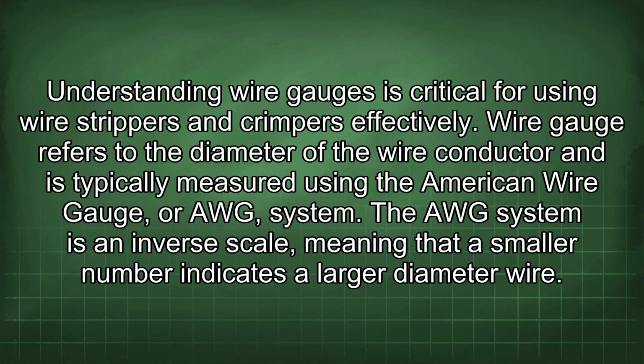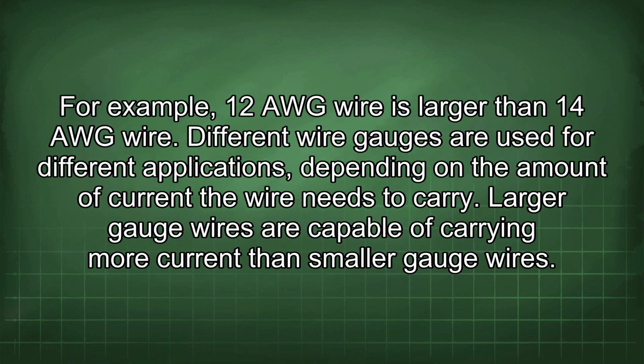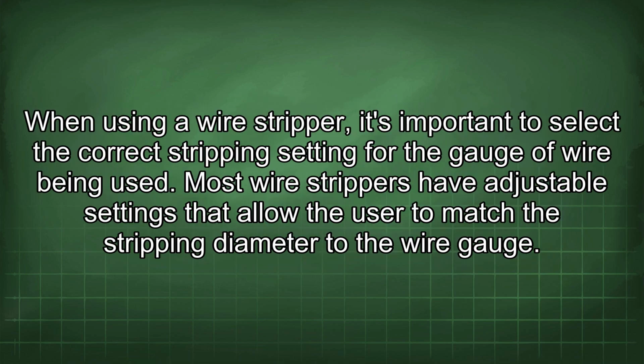Understanding wire gauges is critical for using wire strippers and crimpers effectively. Wire gauge refers to the diameter of the wire conductor and is typically measured using the American wire gauge, or AWG, system. The AWG system is an inverse scale, meaning that a smaller number indicates a larger diameter wire. For example, 12 AWG wire is larger than 14 AWG wire. Different wire gauges are used for different applications, depending on the amount of current the wire needs to carry. Larger gauge wires are capable of carrying more current than smaller gauge wires. When using a wire stripper, it's important to select the correct stripping setting for the gauge of wire being used.